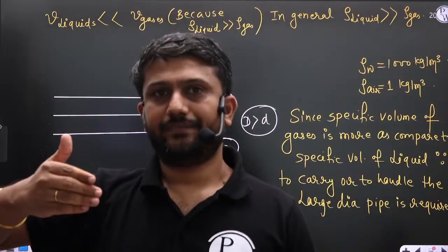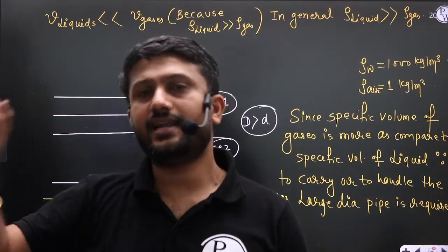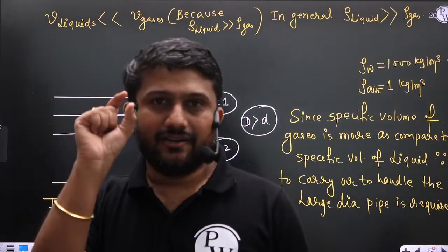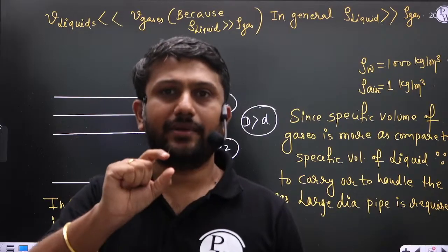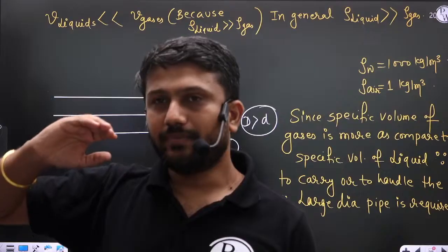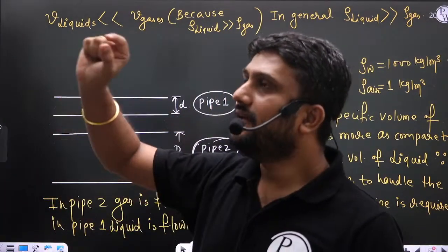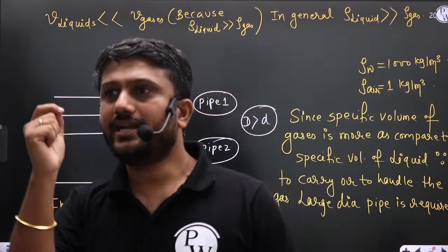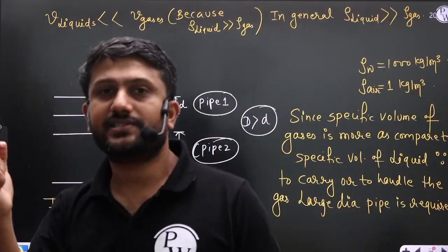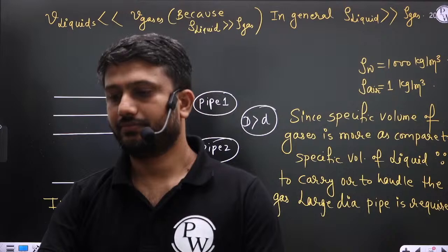In the indoor unit, one pipe has a lower diameter and the other pipe has a larger diameter. So from experience, we can say that the small diameter pipe is for the liquid refrigerant and the larger diameter pipe is for the vapor refrigerant.